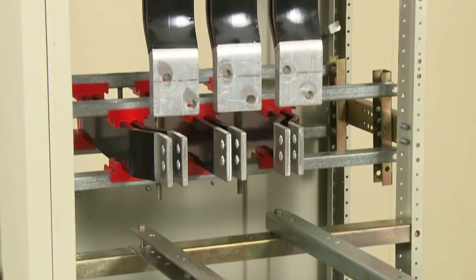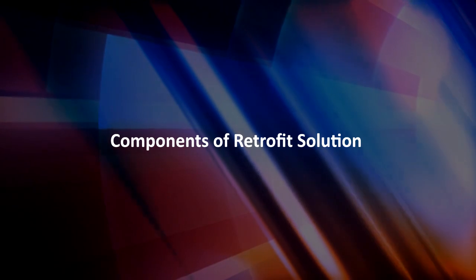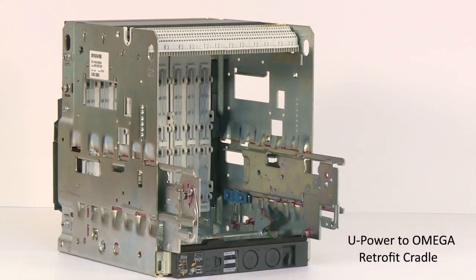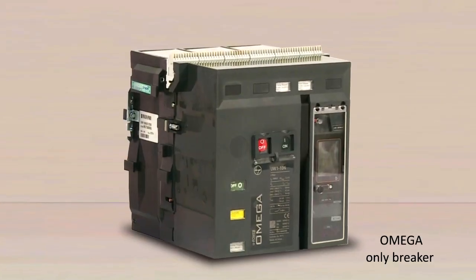We can now clearly see the existing bus bar arrangement. The components required for the retrofit solution are: the U-Power to Omega retrofit cradle, retrofit cradle adapters, and the Omega breaker.